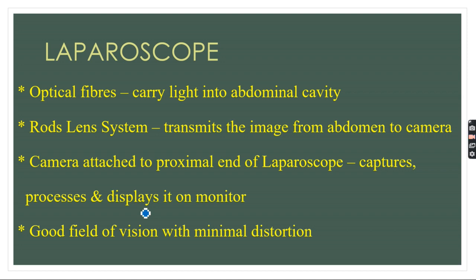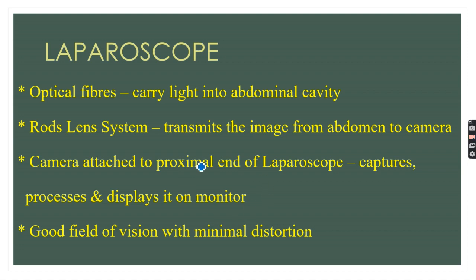The role of optical fibers in the laparoscope is to carry light into the abdominal cavity, whereas the rod lens system transmits the image from the abdomen to the camera. The camera is usually attached to the proximal end of the laparoscope, and its role is to capture and display the image on the monitor. This leads to a very good field of vision with minimal distortion — this is the advantage of using the Hopkins rod lens system.